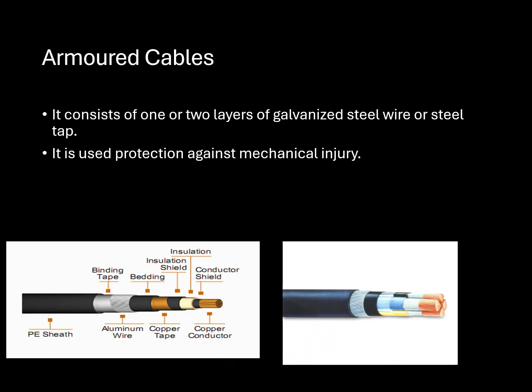Friends, when we say cable, it is generally meant armored cable, and these are laid underground. So an armor is put, which gives it strength. When we don't say armored, then we say wiring cable. The armored cable consists of one or two layers of galvanized steel wire or steel tape. There can be steel wire, circular one, or it can be steel tape. It is used for protection against mechanical injury. That is the main reason.